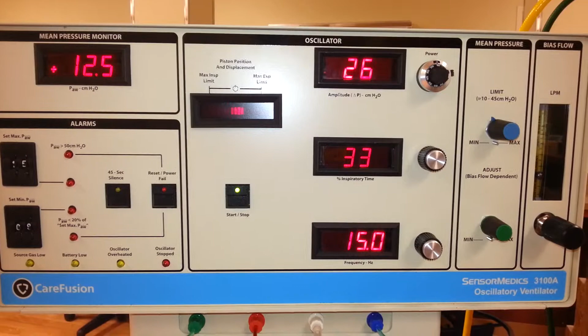Starting on the far right, you'll see the bias gas flow. This is measured in liters per minute and helps to maintain and set the mean airway pressure. Right to the left of the bias flow is the mean airway pressure control here. This is used to set the tension on the machine's diaphragm, which helps to oscillate the gas flow to the patient. The mean airway pressure monitor is on the far left. It is measured in centimeters of water. This helps, along with the FiO2, to control the patient's oxygenation.